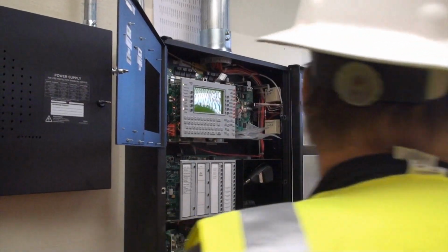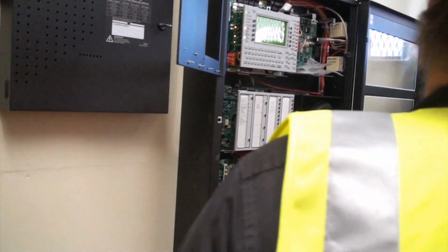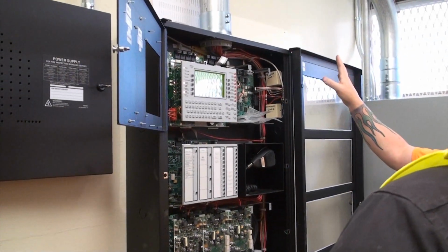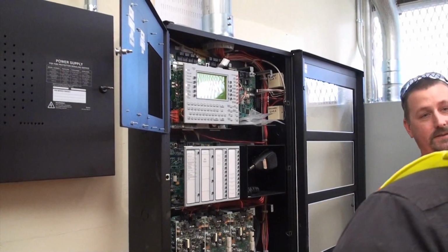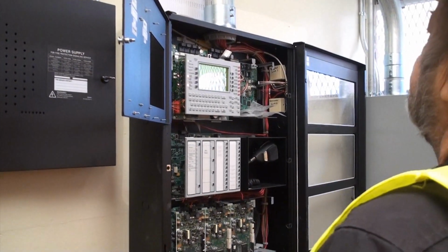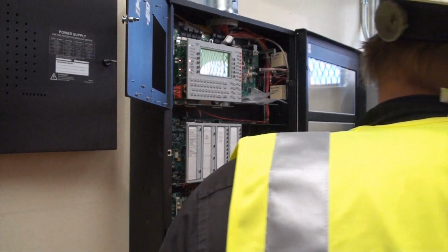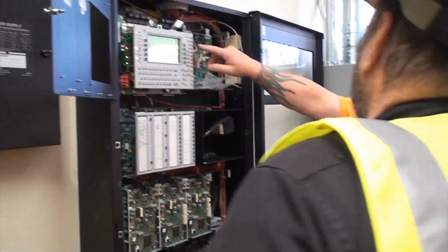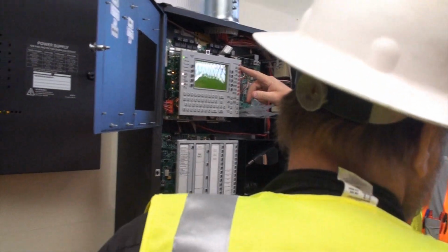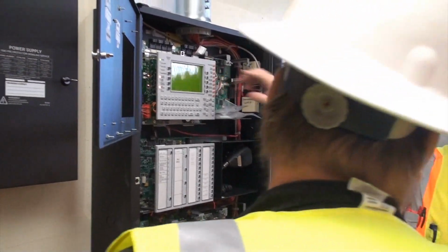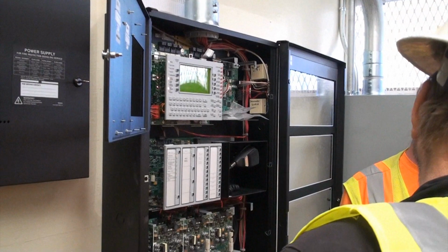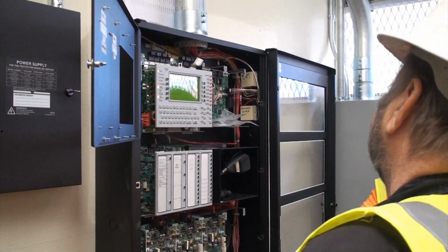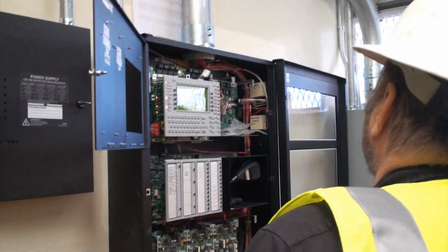Existing panel, yeah. So when this one goes off, it'll trip our panel, sending ours into alarm, and then if we get an alarm in building 200, it'll trip theirs. It'll also put that one in alarm. So if we get one in 400, we'll take care of that one first, then how do you reset this one? So what you'll do is if ours goes off, you'll hit signal silence. That'll shut down the relay too, so you're able to reset and then reset theirs, and then vice versa. Just remember, you guys don't reset.